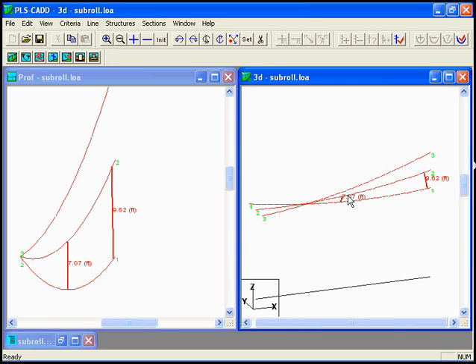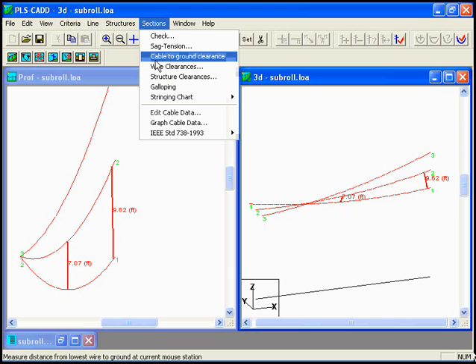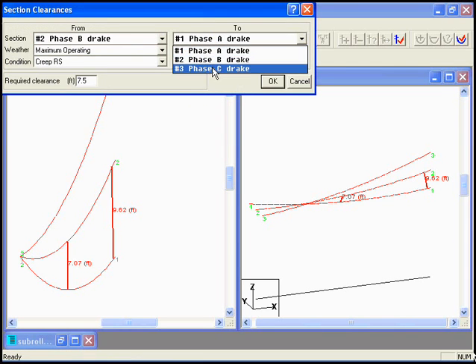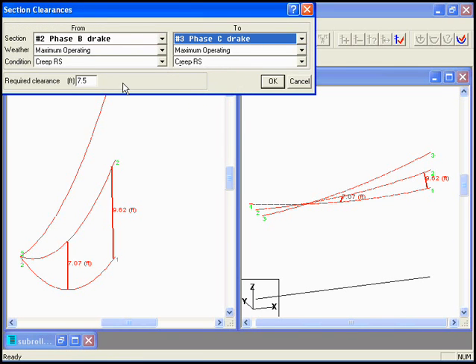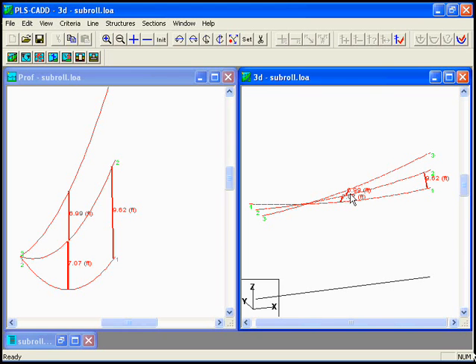While we're at it, let's just go Section, Wire Clearances. And let's go from Phase B to Phase C, again, with 7.5-foot minimum required clearances. We also have a violation of 6.99 feet there. So we can quickly get wire clearances for wires using PLS-CADD Lite. The same function is available in full PLS-CADD and can be done very easily.